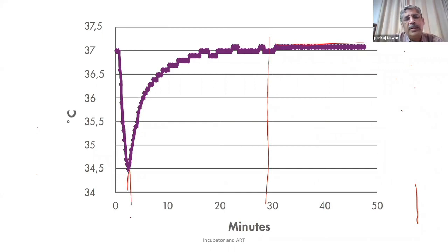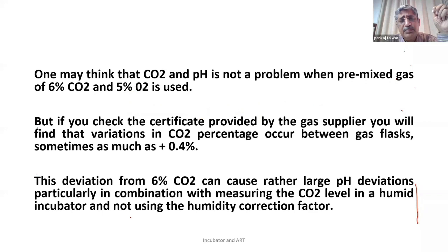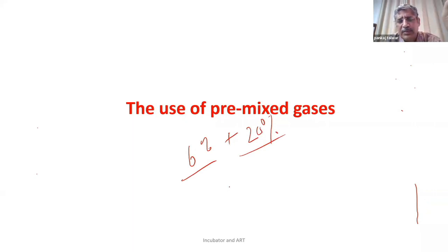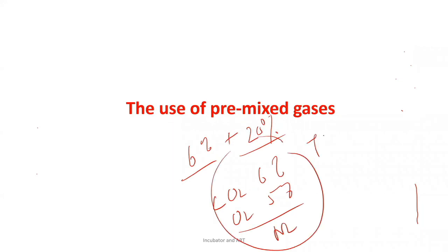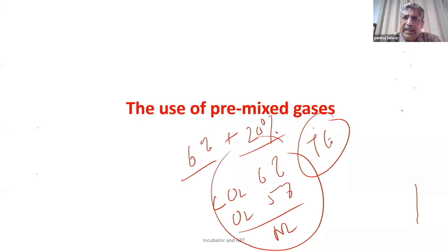One door opening, short as a door opening, can lead to so many problems. So door opening should not be done. The use of pre-mixed gases. Here I'll tell you that initially we were using 6% CO2 and it had 20% oxygen. Then we have shifted to mixed gases now. Tri-gas, about which we have spoken in the class multiple number of times. It has CO2 of 6%, O2 of 5%, and balance of nitrogen. Called tri-gas. And tri-gases are available in the market easily.